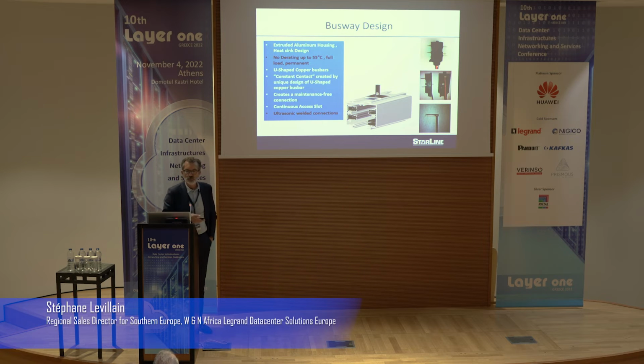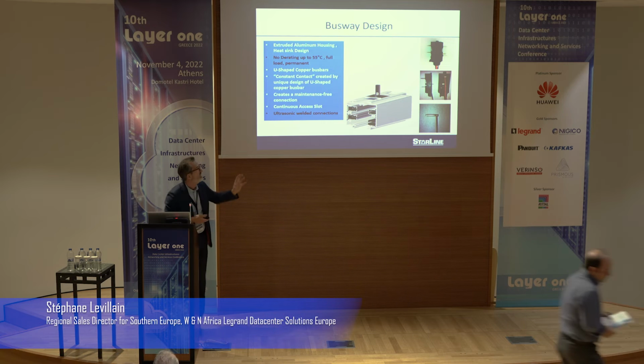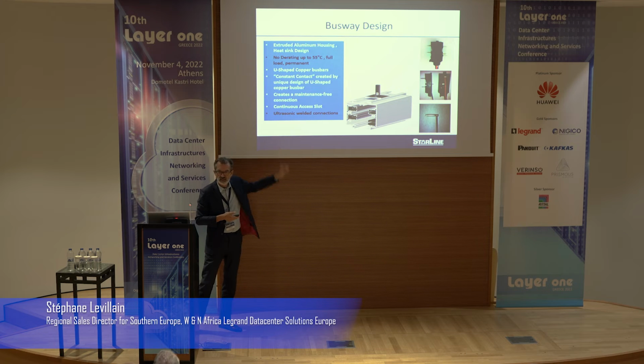We use a U-shaped copper bus bar inside. They are installed in some insulator, and the insulators are installed in a kind of small housing. You can see phase 1, phase 2, phase 3, and neutral. You could also have the ground, isolated if you will, as an option. It's not a problem. And what you see, the black piece, we call that the paddle in English. This is the head of the tap-off that you will insert in the busway.